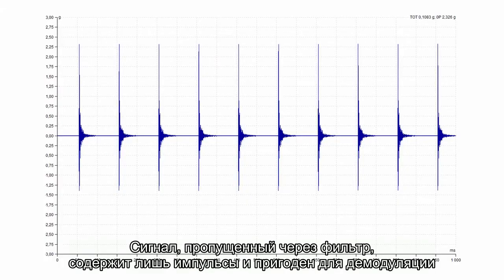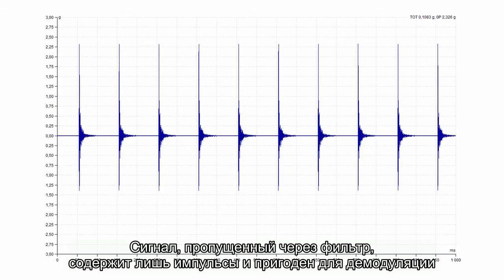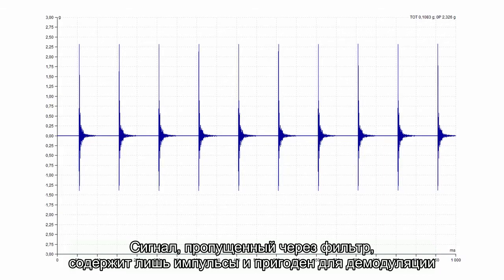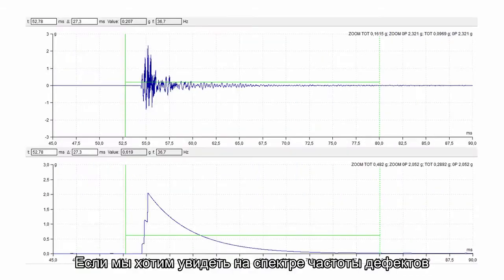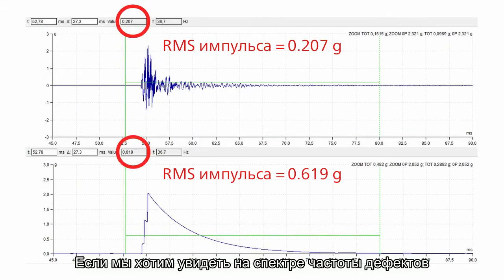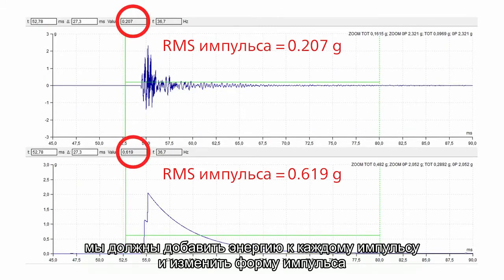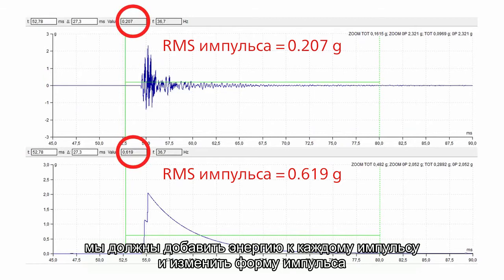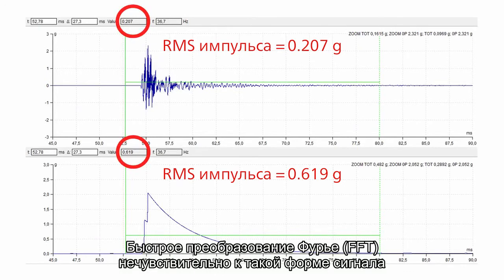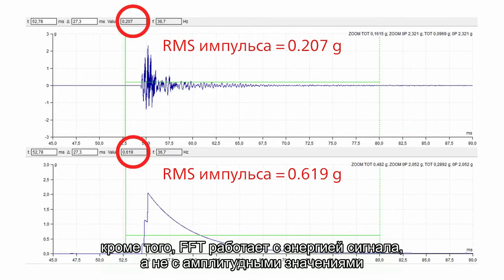Filtered signal contains just shocks and is ready for demodulation. If we want to see fault frequencies in spectrum, we must add the energy to each shock and change the shape of shock. Original shape is too much variable. FFT is not sensitive for such shape. And the FFT works with signal energy, not with the peak values.